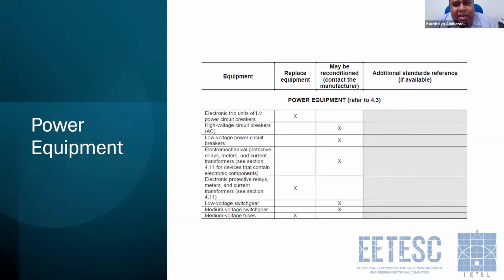Power equipment, all electronic trip units, replace. High voltage circuit breakers, you can rehabilitate. Low voltage power circuit breakers, what are these? Are they MCCBs? No, they refer to ACBs. ACBs you can recondition. Electromechanical protective relays, meters and current transformers, yes, you can rehabilitate or recondition. Electronic protective relays, meters, current transformers, that means CBCTs and all, you have to replace.